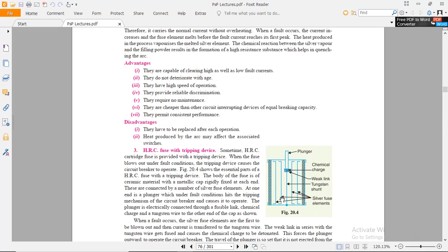When the fuse blows out under fault condition, the tripping device causes the circuit breaker to operate at a certain time, as mentioned in the figure, where the plunger is connected here. Further, the chemical charge is imposed here, with a weak link also available there after that chemical charge. The tungsten shunt is also there. The silver fuse element is also connected in these lines. So this shows the essential parts of the HRC fuse with the tripping device.